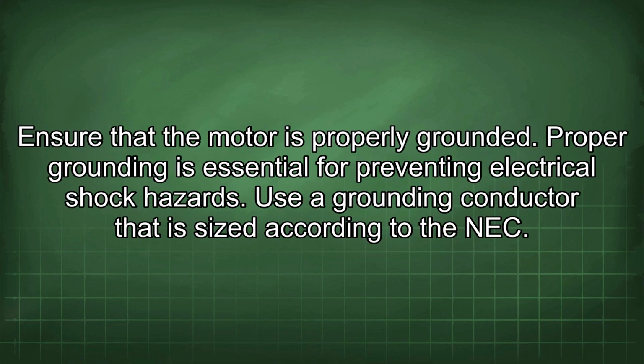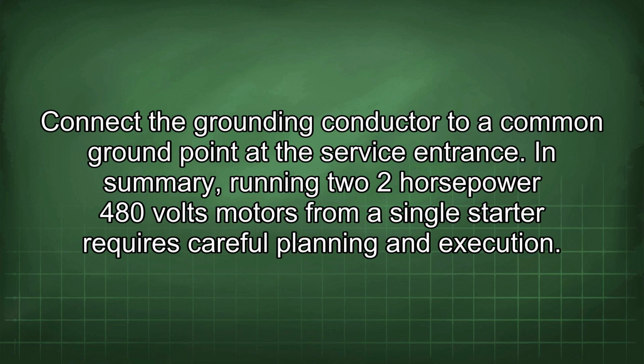Ensure that the motor is properly grounded. Proper grounding is essential for preventing electrical shock hazards. Use a grounding conductor that is sized according to the NEC. Connect the grounding conductor to a common ground point at the service entrance.